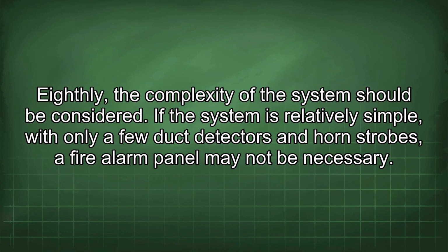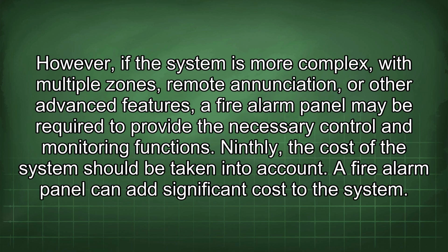Eighthly, the complexity of the system should be considered. If the system is relatively simple, with only a few duct detectors and horn strobes, a fire alarm panel may not be necessary. However, if the system is more complex, with multiple zones, remote annunciation, or other advanced features, a fire alarm panel may be required to provide the necessary control and monitoring functions.